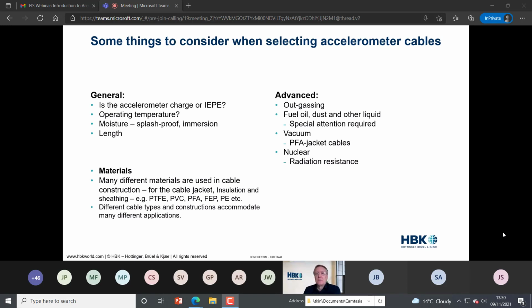And there are some advanced considerations you might very occasionally get into, depending upon your field of work. Some cables produce gas when they get to a certain temperature. Some cables will be attacked by nasty substances, fuel oil, etc. If you're in a low pressure environment or a vacuum, you need to choose your cables carefully. And similarly with radiation present in the field, you need to make sure that your cable, as well as your accelerometer, is resistant. There are lots and lots of different types of cables made from different materials, for the simple reason that different applications need different cables.